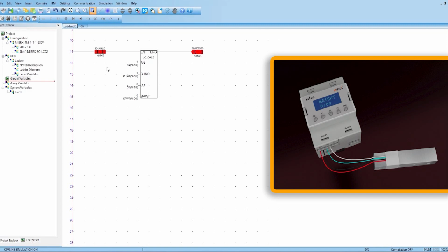Now, let's begin the calibration procedure. For 0 calibration, ensure no weight is placed on the load cell. Set calibration code 0. Set span weight as 0. Trigger the enable bit. When calibration bit is on, then only known weight calibration is done.